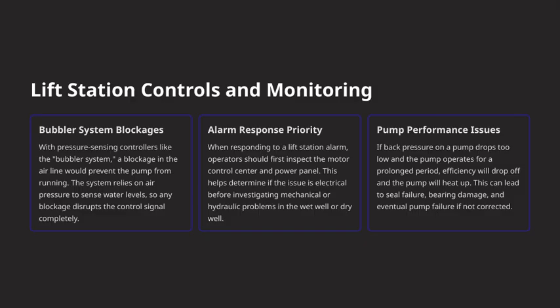Finally, let's discuss pump performance issues. If the back pressure on a pump drops too low and the pump runs for too long, efficiency drops, and the pump starts to heat up. Over time, this can lead to seal failure, damage to the bearings, and ultimately, pump failure if we don't act. So, keeping an eye on pump operation and addressing low back pressure early is crucial for maintaining reliable system performance. Connecting all these points, it's clear that vigilant monitoring and timely responses are essential parts of effective lift station management, ensuring everything runs smoothly and avoids costly repairs.